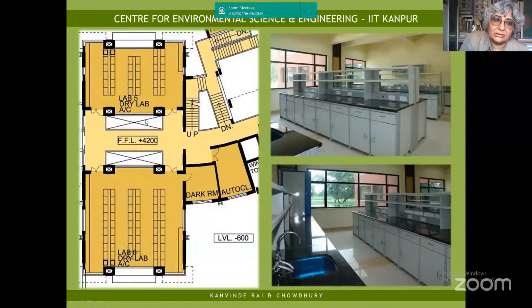These are the service shafts that one had looked at. The wet services were on the outside, easy to access, in the labs. And because of the earth air tunnel, we managed to reduce the AHU size substantially, since we were bringing in the outside 40-degree temperature air.